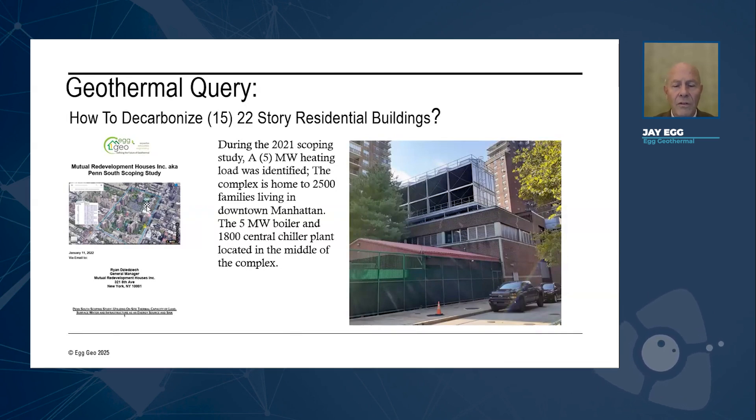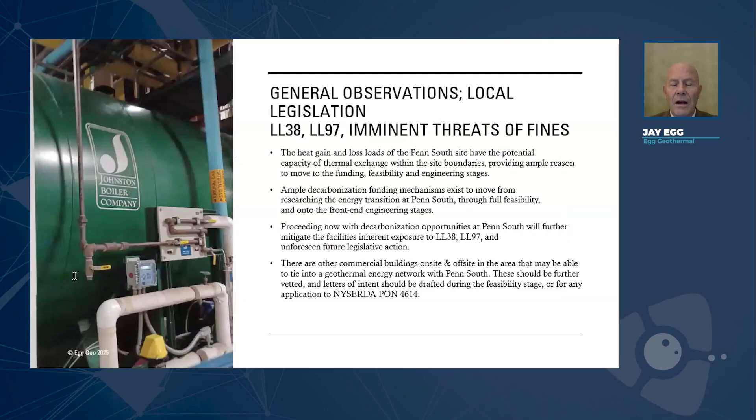We did our first study in 2021 on that, and it netted a great deal of information. We then applied for a state grant, which basically asked: how can we decarbonize these buildings with drilling as few holes as possible? The industry typically knows that with geothermal technologies you need one borehole per two or three tons. This being an 1,800-ton, five-megawatt load would mean it would need literally hundreds, if not thousands, of boreholes — which is cumbersome and messy. So they asked: how few boreholes can you use to decarbonize this and turn off this five-megawatt boiler?